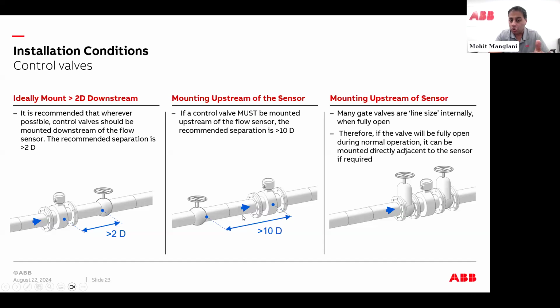If you have a control valve upstream, say a butterfly valve, the butterfly valve is the hardest one, because you already have a valve in the middle of the piping, and that's automatically going to cause a disturbance in your laminar flow. So we always say for a butterfly valve, give us 10 upstream. But if you have gate valves that are always open, unless you have to isolate something, you can put the meter right next to the valve, because most of the time those are fully open, full bore valves. So just keep in mind the installation conditions of whatever's upstream and downstream of the meter.